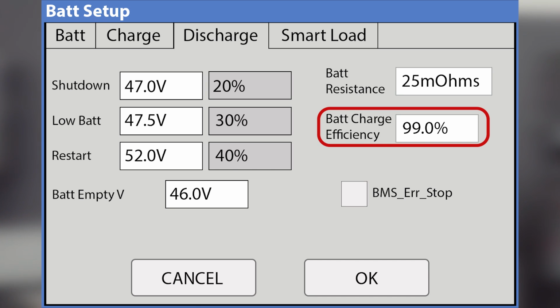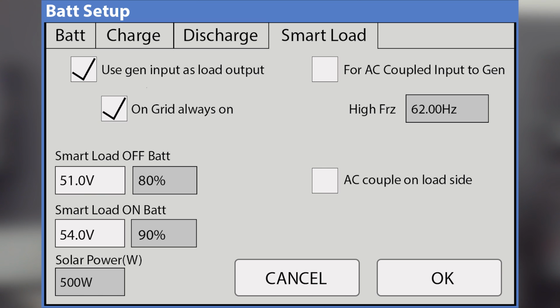another spec you'll get from your manufacturer. And smart load, I'm not going to go into tons of detail here because this is just a quick commissioning video, but this is going to allow you to control the generator breaker. The generator breaker is both an input or an output, depending on what you program it to. And this is where you're going to adjust those settings. So you can either put AC coupling in, you can put a generator in, or you can use it as a kind of load shedding output.